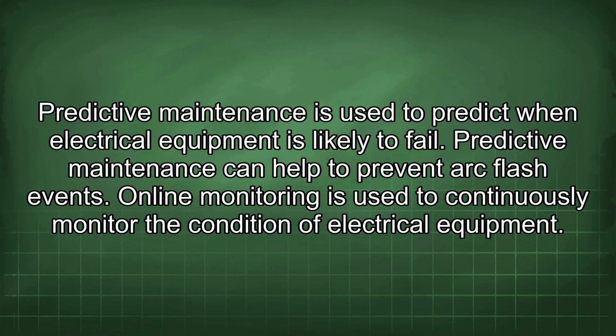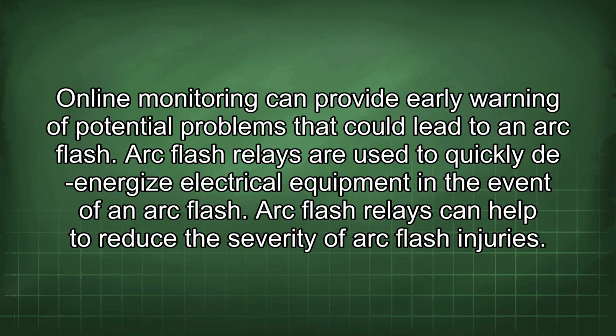Online monitoring is used to continuously monitor the condition of electrical equipment. Online monitoring can provide early warning of potential problems that could lead to an arc flash. Arc flash relays are used to quickly de-energize electrical equipment in the event of an arc flash. Arc flash relays can help to reduce the severity of arc flash injuries.